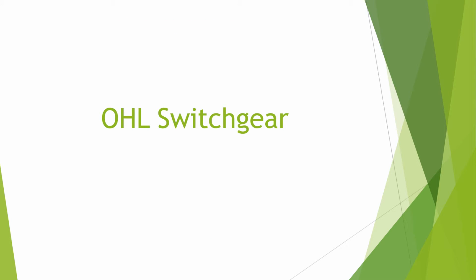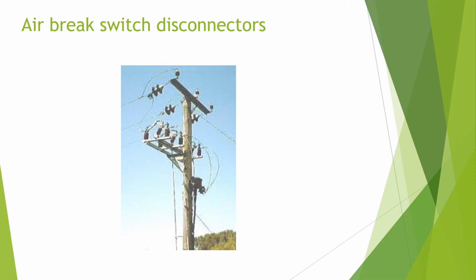Overhead line switchgear. Overhead line circuits require means of isolation and protection. Rather than use ground-mounted units, switchgear has been developed to be mounted at high level on poles to provide these functions. Air break switch disconnectors, or ABSDs, are a relatively cheap method of isolating sections of line or items of plant such as circuit breakers or transformers.